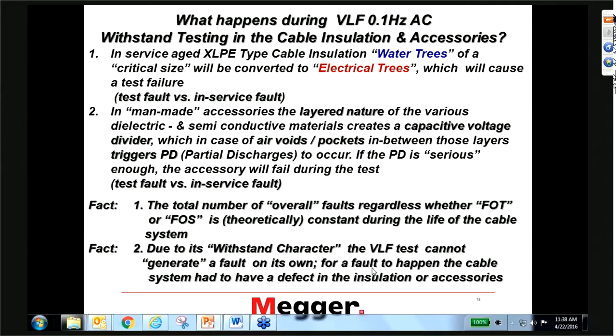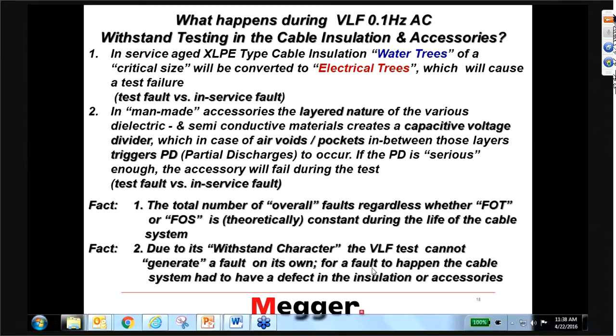The initial 60 Hz AC test was 2 per unit. The VLF test is 3 per unit. These values have been used for many years and have proven to be very appropriate.